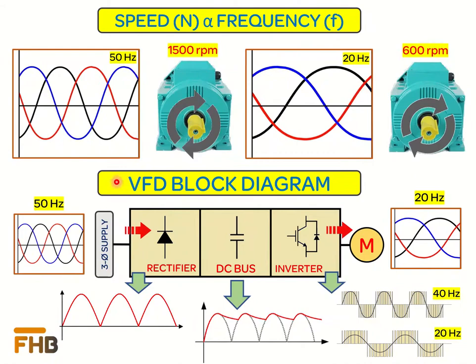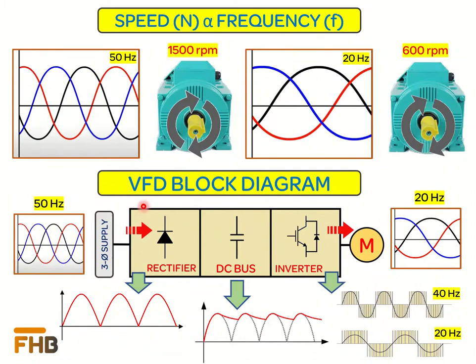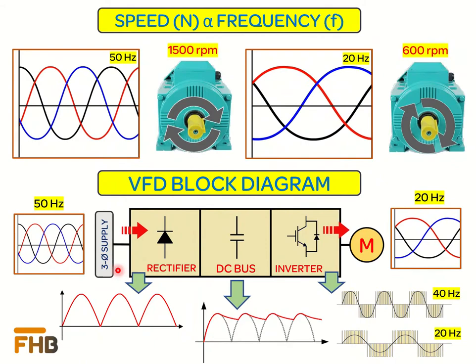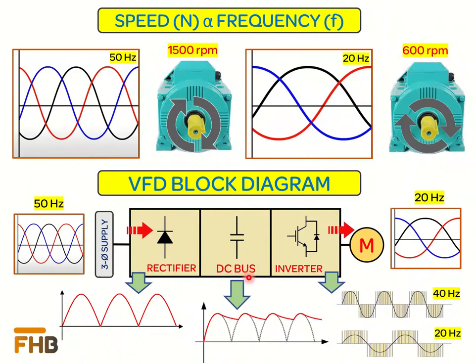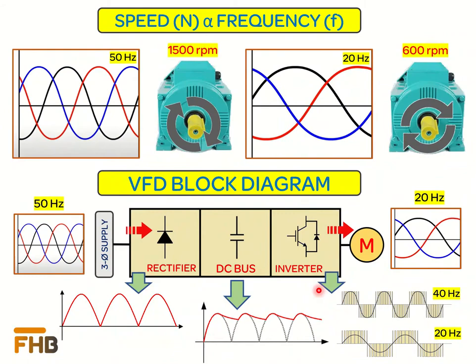We will now see how a variable frequency drive controls the frequency of the power supply. To control the frequency of the incoming waveform, the design of the VFD typically consists of three stages. The first stage is the rectifier, which uses diodes to convert the AC signal into a pulsating DC signal. In the second stage, ripples in the pulsating DC waveform are filtered using a capacitor, producing a relatively smooth DC signal.